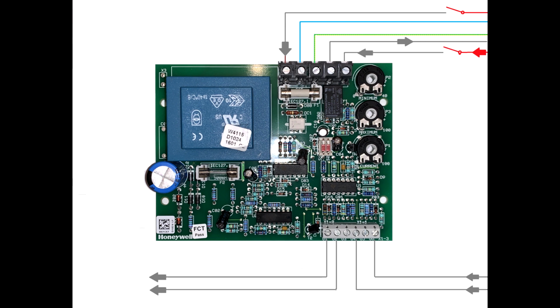That signal can come from a programmable logic control, or from a building management control, or can even be a switch. It could be connected in series with a group of alarms like fire alarms, supply fan differential pressure switch, or any other type of alarm like high temperature limit, etc. But let's see how this printed circuit board works.